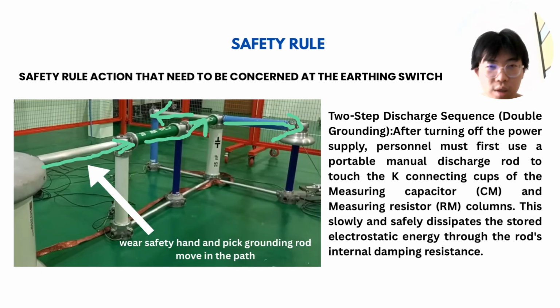Now I will talk about the safety rules and the safety actions that need to be observed at the earthing switch. Before we do this, we need to wear safety gloves and pick up the grounding rod. The first safety rule is a two-step discharge sequence with double grounding. After turning off the power supply, personnel must first use a portable manual discharge rod to touch the connecting cup of the measuring capacitor CM and the measuring resistor RM column. This slowly and safely dissipates the stored electrostatic energy through the rod's internal damping resistance.